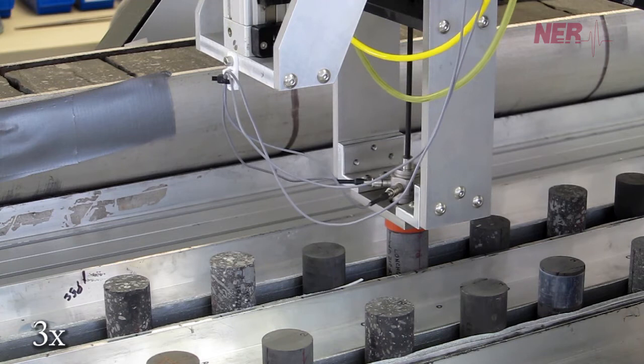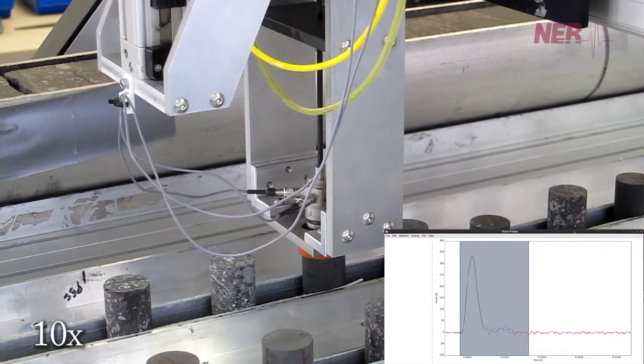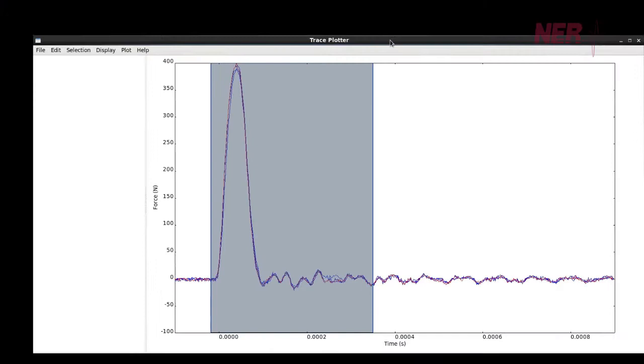Shown here are the output force curves of four measurements made on a single plug. Each measurement is made at a new location 2mm from the previous measurement.